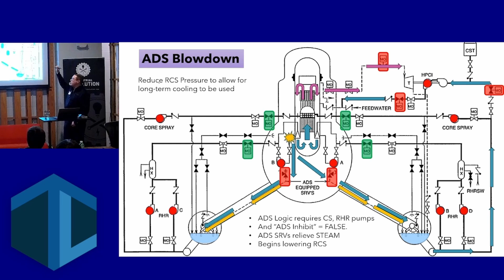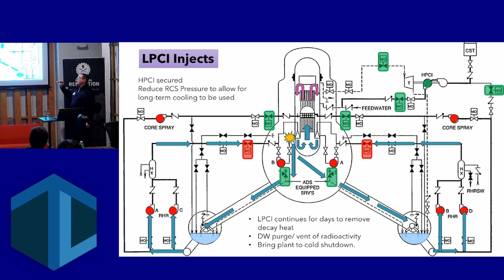HPCI will be secured because we're now below 200 pounds in steam pressure, so I can't use it any longer. And that's okay because now I have this super redundant, very reliable RHR system, also known as residual heat removal system, where I can push all the water in these heat exchangers. These are cooled by the Susquehanna River itself, so I can reject almost infinitely amount of heat for many, many days. Our cooling system is designed for safety-related mission time of 7 days, which is way longer than you need, but you never know what happens.